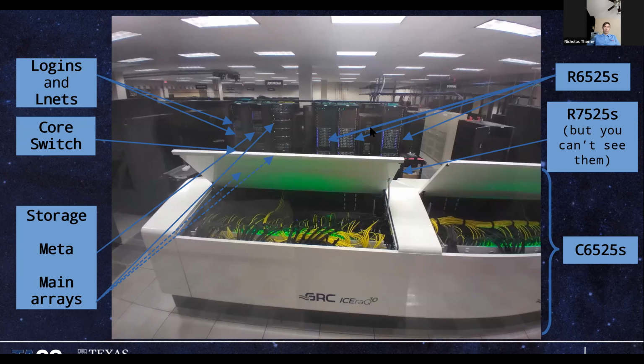So we would have been installing many, many more of these in-row coolers. We may have had to go with a solution like actively cooled rack doors. And for a system of this size, approximately 500 nodes, that's not really a cost-effective solution. So this is Lone Star 6, and some of the design decisions that we were trading off at the point in time that we designed the system.